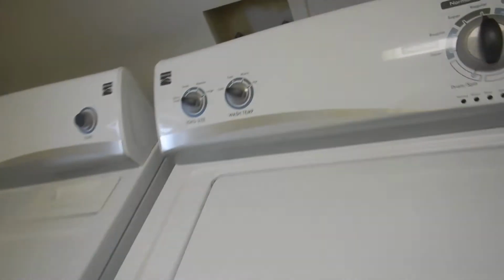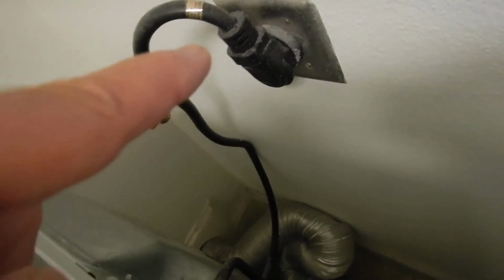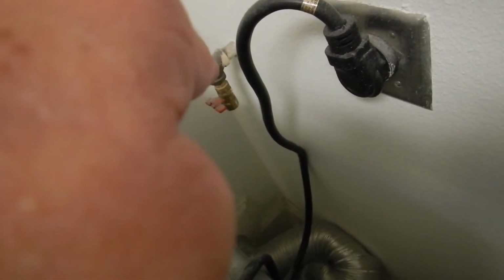Middle south bedroom, middle north bedroom, north bedroom. Laundry. No GFCI. No GFCI. No GFCI. The gas supply right there should be capped off. If you're not going to use gas, it should be capped off. We do not have a safety pan and drain for the clothes washer. And then outside on another video, you can see that the clothes dryer vent is clogged.